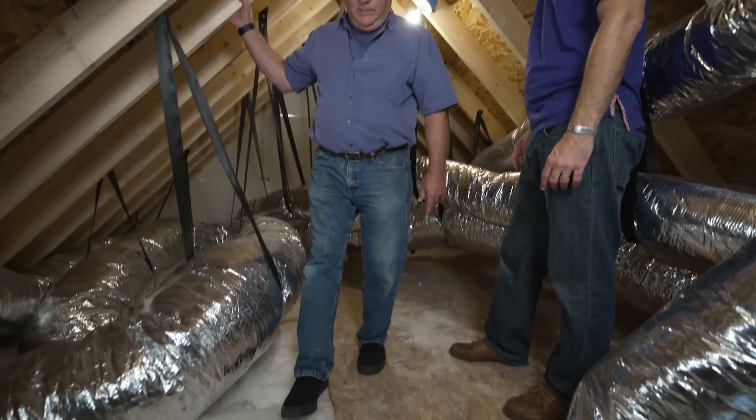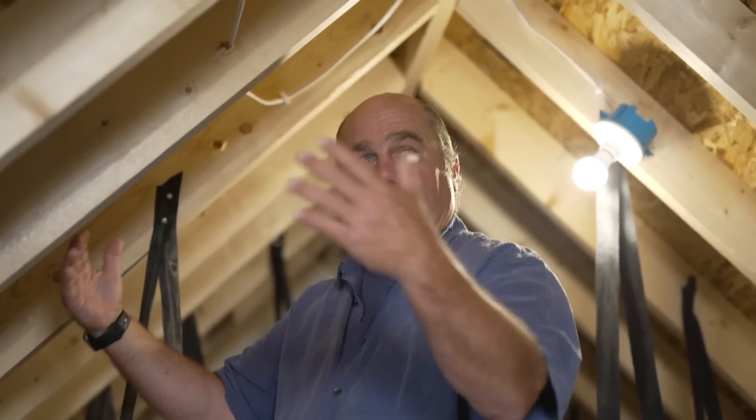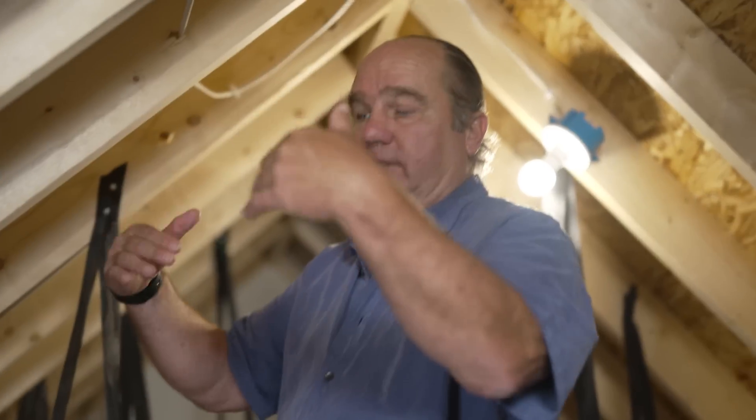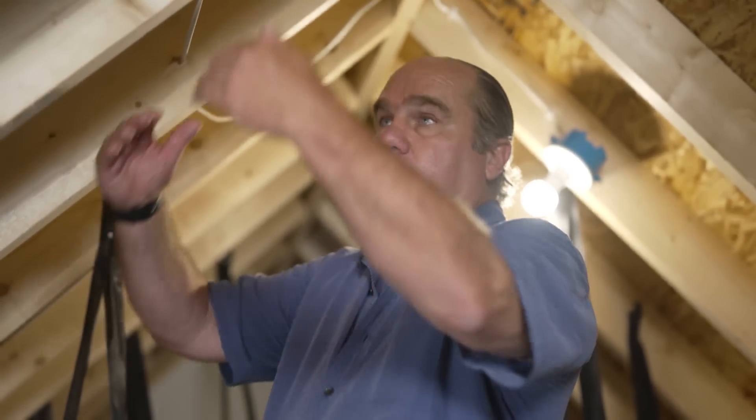If you notice right here, you get insulation in the ceiling of the second floor, and then there's an uninsulated roof. Now that means — how hot does it get in your attic? At least 120 degrees. So that sun's beating down, this is trying to cool the air, and in every off cycle it just sort of heats — superheats the ductwork. So I always recommend insulating here.